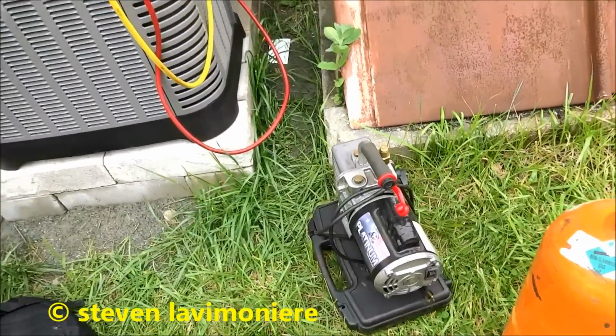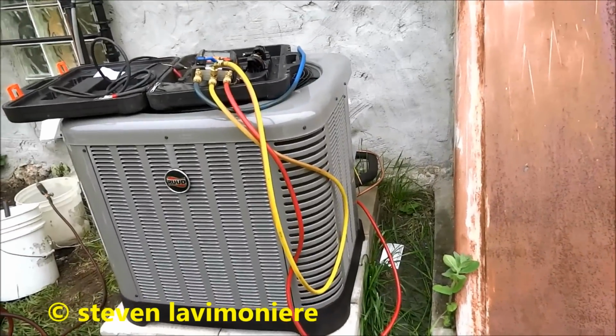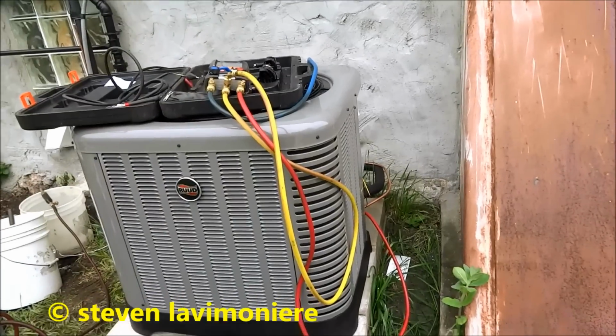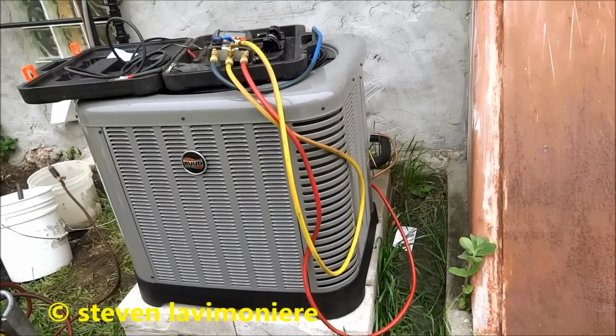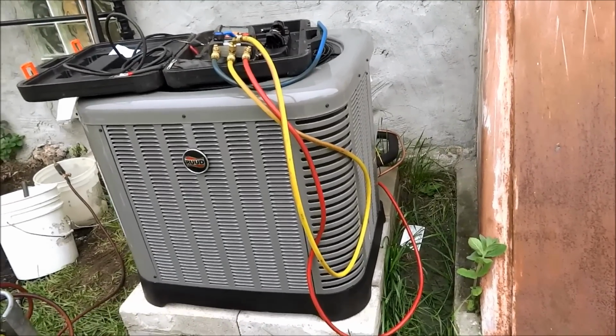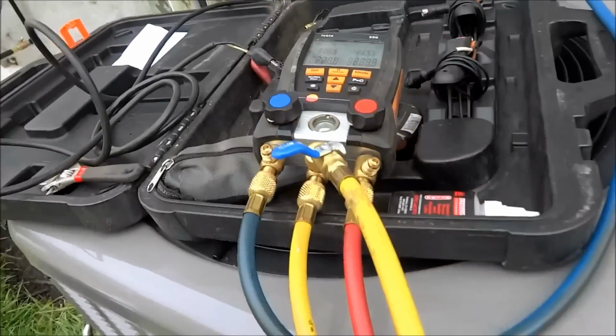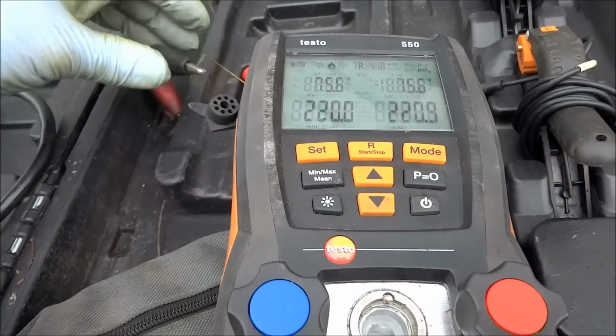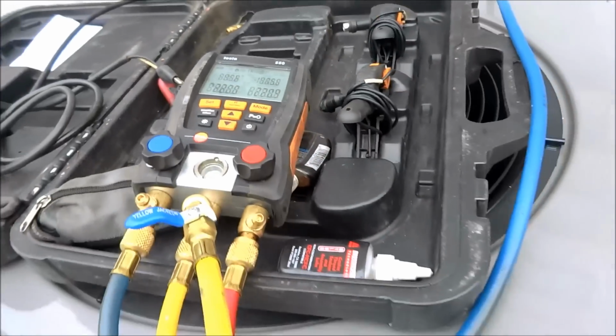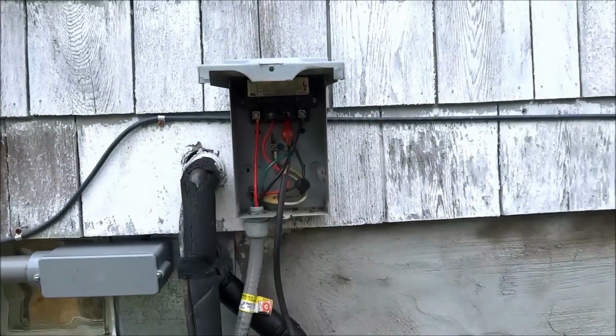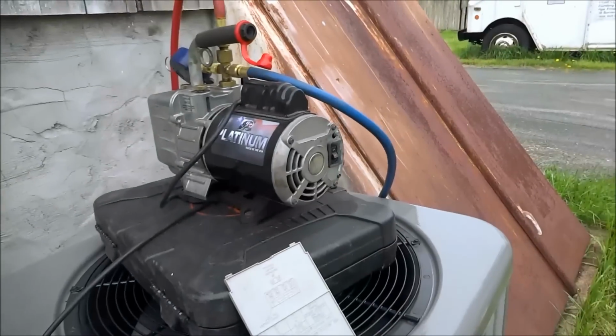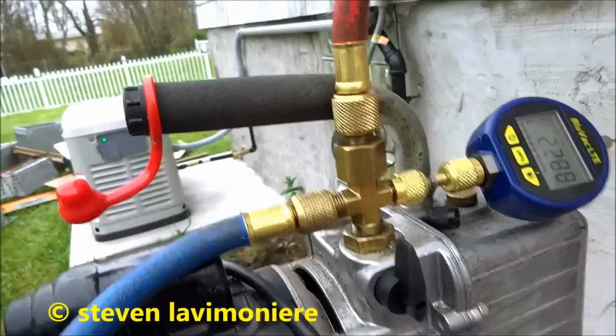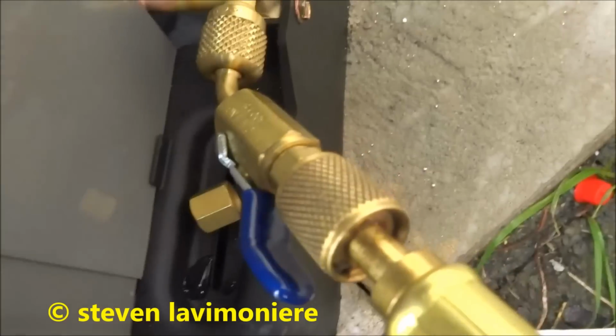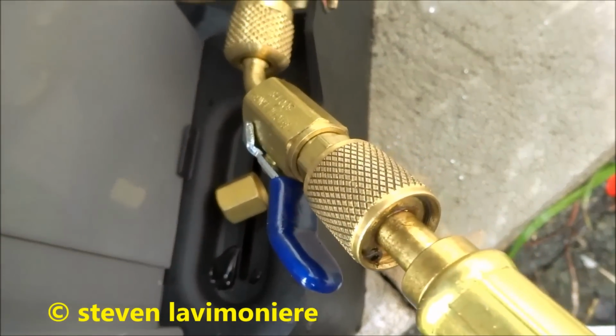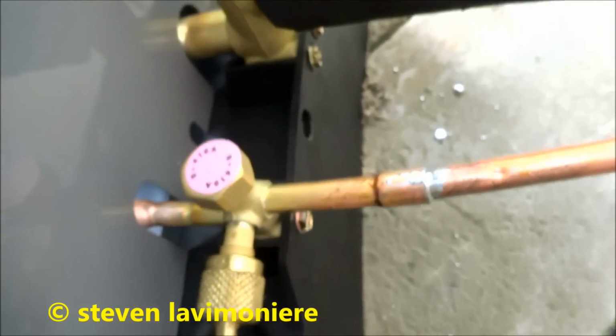I got my vacuum pump here, we'll get that going, pull that vacuum down and release that gas. Probably tomorrow I'll run the electrical and the drain line, hook up the thermostat wiring and stuff. Just grab power out of the box. Got the little shut-offs right there. I can shut it off after the vacuum's pulled, and I can release the gas.